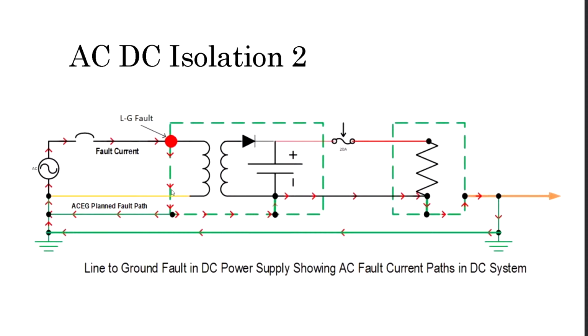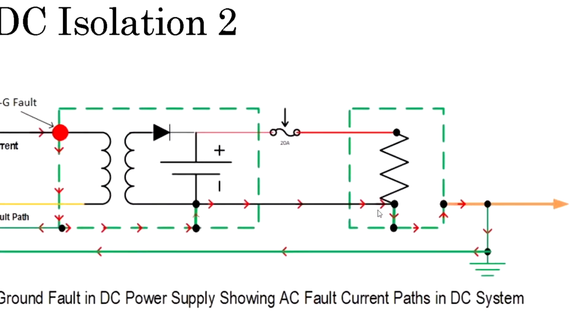One, in the chassis, it returns back onto the AC equipment ground, the one that's planned and intended for it, goes straight back to the utility. But with that bond in the power supply to the negative, there's a second path. It gets on our DC negative, it goes to our radio. It goes through our radio equipment out on the coax, back to out here onto the earth ground, comes all the way back through the earth ground to get back to the utility transformer. Okay? That's not good.